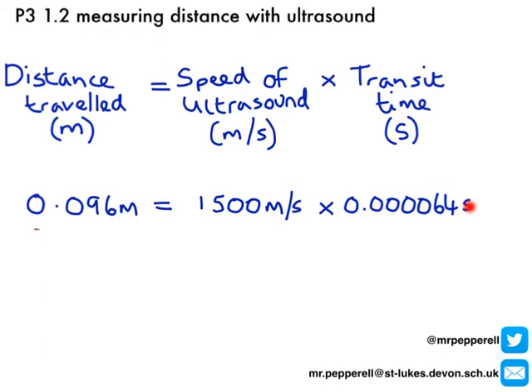I've recorded on my A-scan a transit time of 0.000064 seconds. I can multiply those two numbers together, and the product — 0.096 metres — is the distance my pulse has travelled. And 0.096 metres is the same as 9.6 centimetres or 96 millimetres, which is a reasonable distance. When doing these, think about the number you get and ask: could that number be inside of an eye?